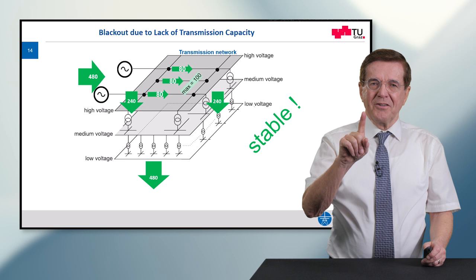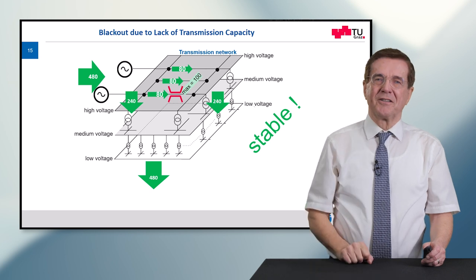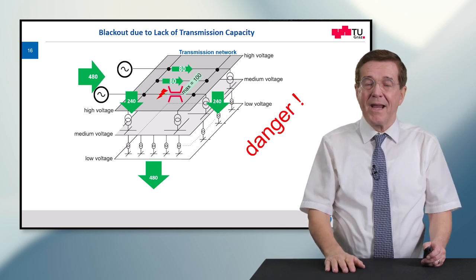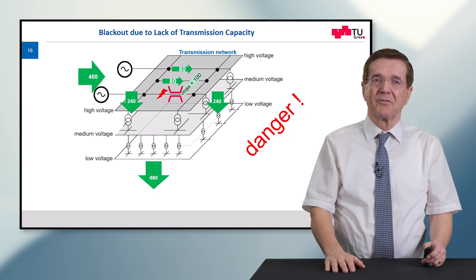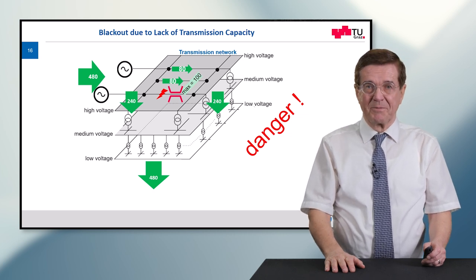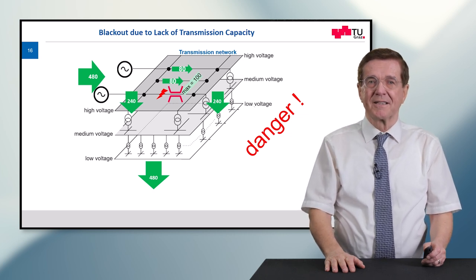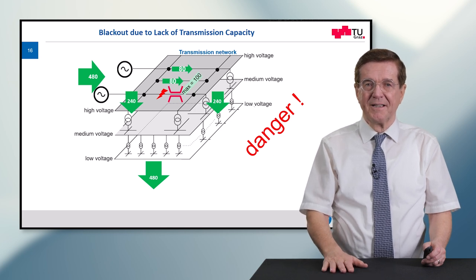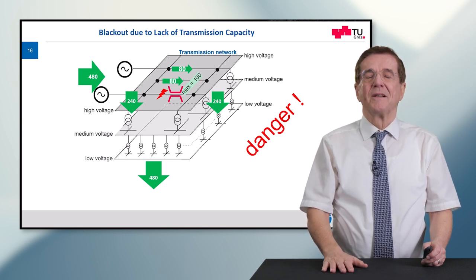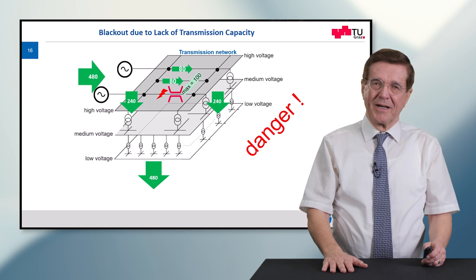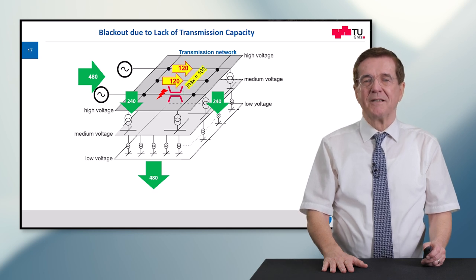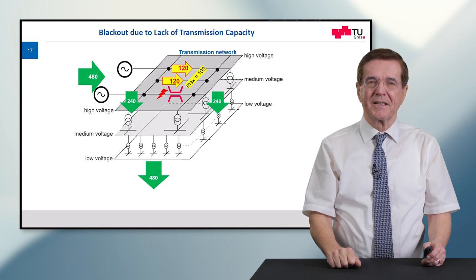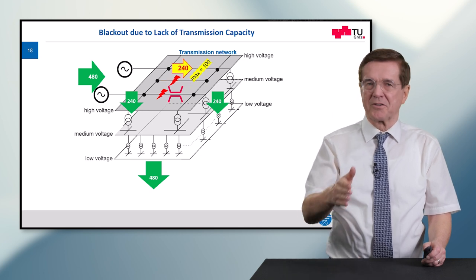What I did not mention yet is that the first line has a bottleneck problem which may lead to a short circuit and will trip out this first line — this is the danger point, this is where it starts. The power that flows from left to right will now be split between the two remaining lines, which immediately go on overload and will trip out.